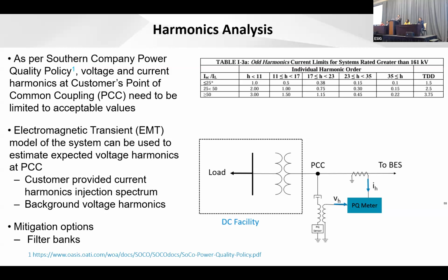So what we are doing is asking for that information upfront, like what the expected harmonic spectrum is. Then you can build a computer model, like EMT, or for harmonics it could be a frequency domain model. Once you have that model and the current harmonic spectrum information, you need to know your existing background harmonics. Then it's possible to estimate what the harmonics would be when the facility starts operating.